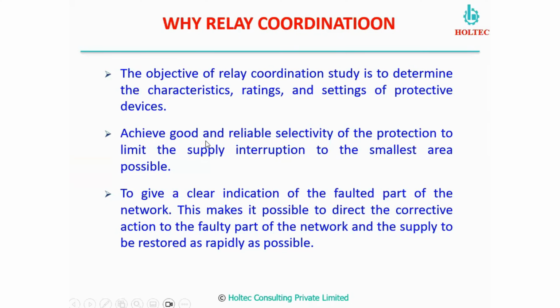It is not only that. In many plants, when we have proper relay coordination, we get the diagnosis of the fault, the diagnosis of the faulty zone. We can clearly define the area where the fault has happened, so my total efforts will be confined to that faulty area only. Suppose no relay coordination is there, then there will be a bigger area which we have to investigate, and maybe it is not only one equipment.